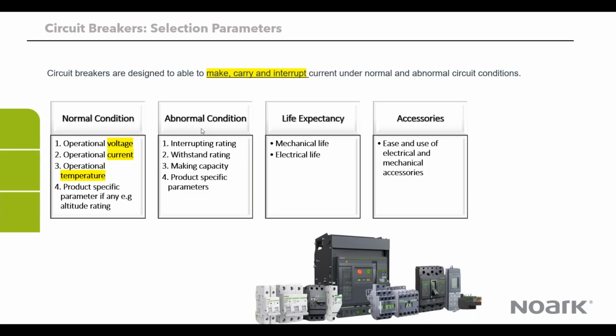When the engineers are designing the system, they're going to do what we call the fault level analysis, where they find out what the fault level is at every level of installation in the system. It's rated in kiloamps, because it's in thousands of amps. So when you find what that fault current is, you make sure that your circuit breaker is at least equal to or more than that fault current.